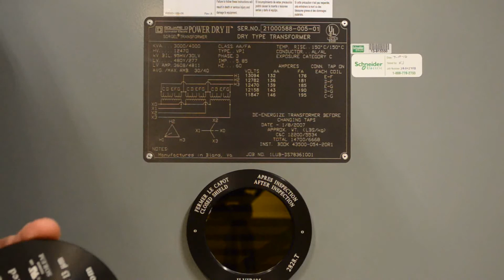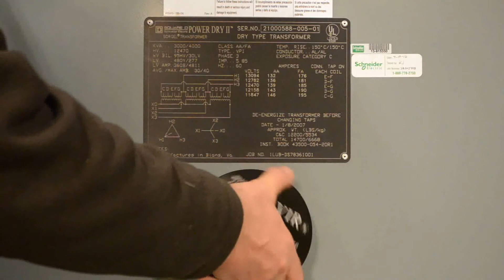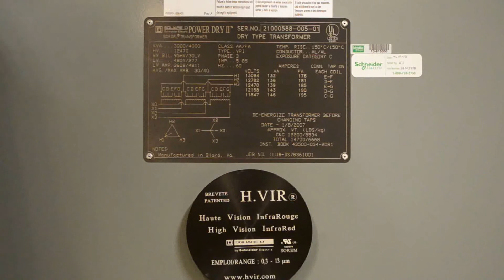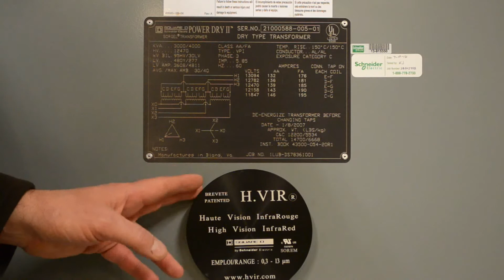Below that, we have installed a product that we make: an infrared window. This allows us, and our customers, to remove this bezel and take pictures with an infrared camera, which can tell us hot spots or cold spots on the coil. If there's an issue, we can go in and do preventive maintenance, or it can be a predictor for possible failure. It's a really good product that's helped improve safety in the electrical industry, and we use it on all of our transformers here.